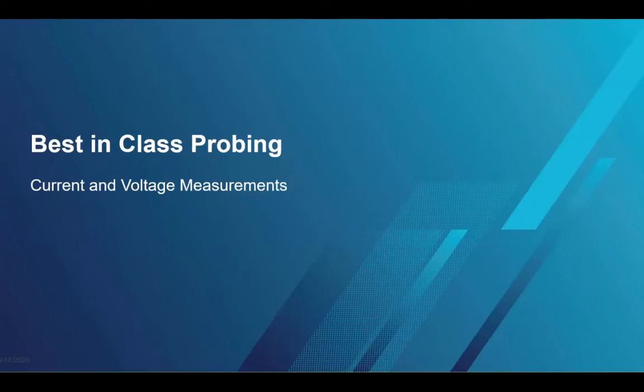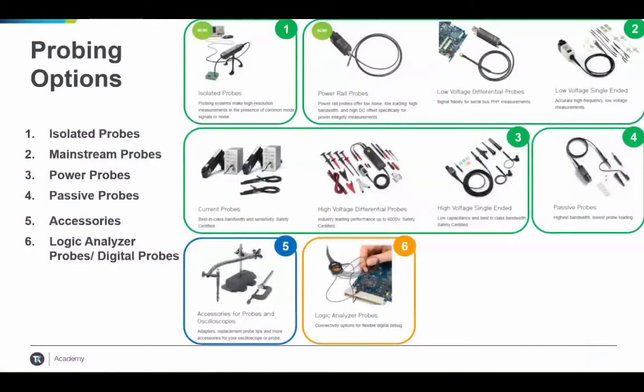The scope cannot be used alone — you need probes to capture voltage and current signals. Typically, you would use a high-voltage differential probe, which normally has bandwidths up to 200 MHz, more than enough for motors running at low frequencies. For higher bandwidth needs, isolated probes are available going up to 800 MHz or 1 GHz. For current, there is a range of current probes available measuring from 30 amps all the way up to 2 kiloamps. You must choose the right probe for your measurement before connecting to your system.